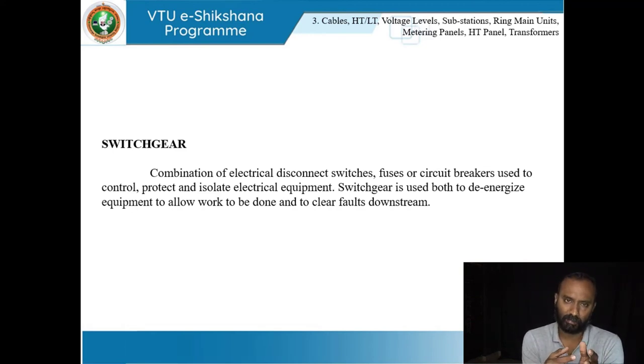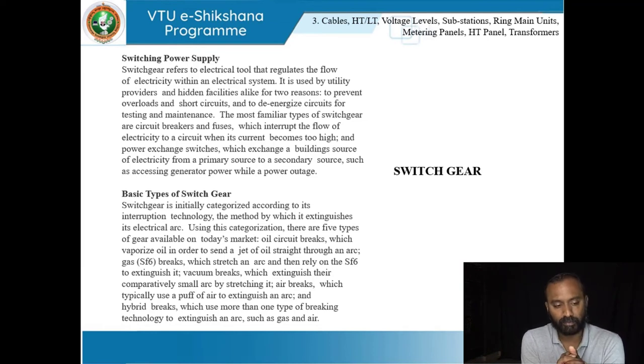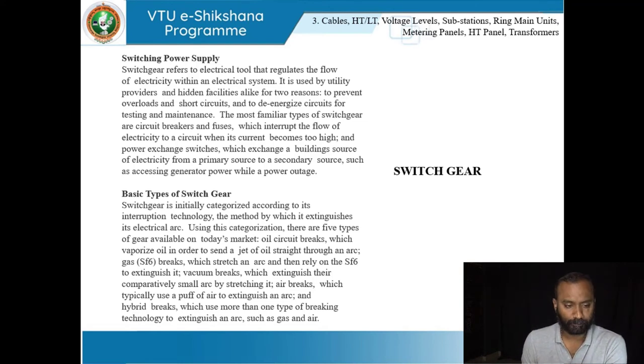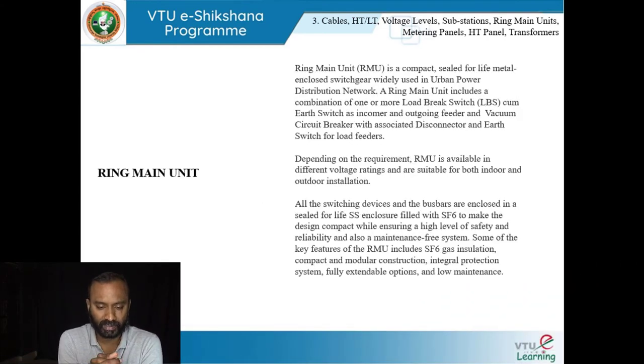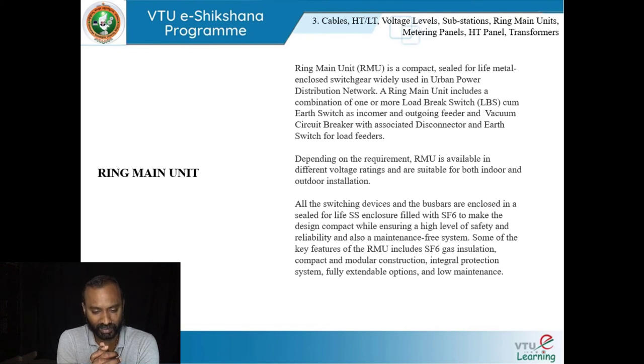Switchgear can be imagined as a complicated switch. There are basic types of switchgear covered here; we will come back to some of these in module three on protective devices. A Ring Main Unit is a compact, sealed-for-life, metal-enclosed switchgear widely used in urban power distribution networks. It includes a combination of load break switches, earth switches as incomer or outgoing feeders, vacuum circuit breakers with associated disconnectors and earth switches for load feeders, available in different voltage ratings.